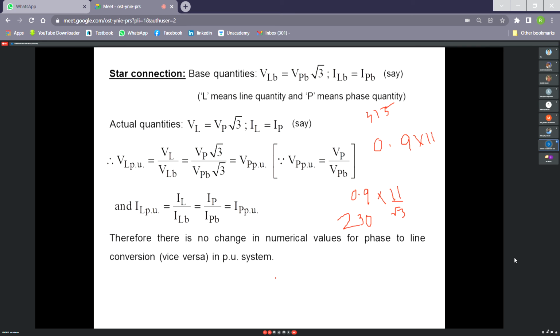At the same time, you cannot assess that easily. I hope you have the concept that in transmission lines we generally allow 5% voltage drop, is it not? So 5% voltage drop, with 1 per unit meaning 100%, means the voltage must be between 1.05 and 0.95 in per unit.